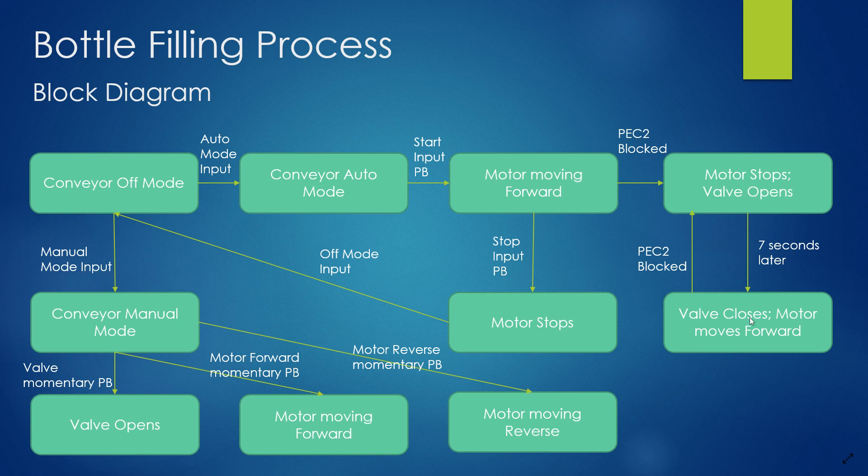Seven seconds later, valve closes, motor moves forward. When the middle photo eye is blocked again, motor stops and valve opens. And this continuous operation stops once we hit the stop input push button.